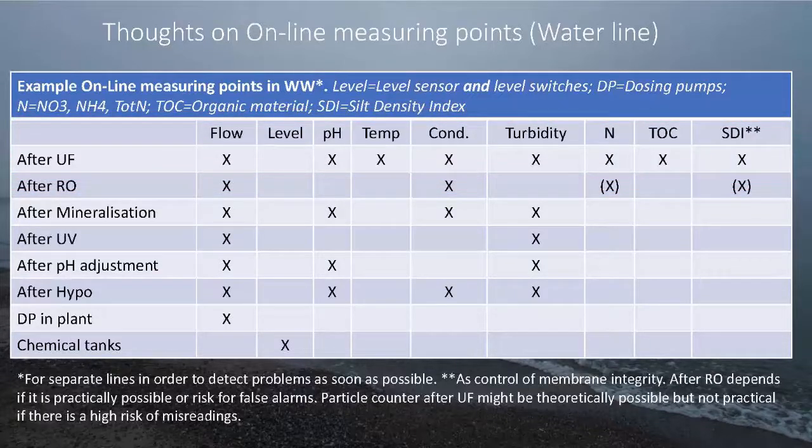After the UF I would check the flow, the pH, the water temperature, conductivity, turbidity, nitrogen, organic material and also maybe SDI silt density index. So a number of online measurements but this is our first good barrier. So here we need to have good control over what's coming out of it.